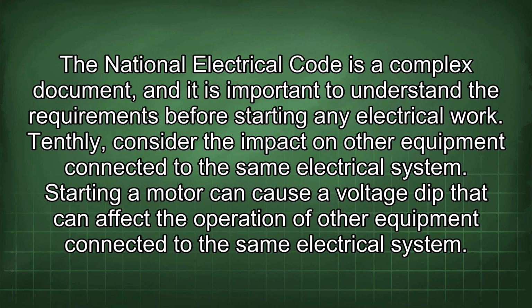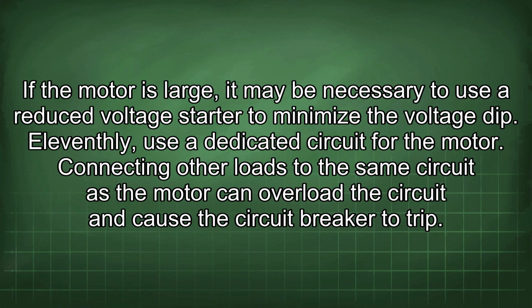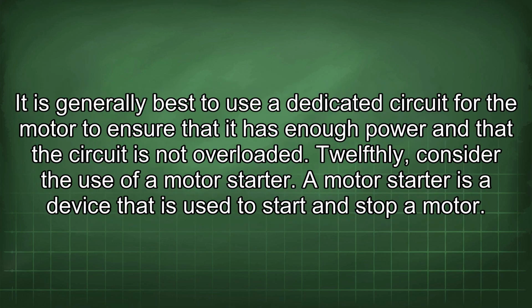Starting a motor can cause a voltage dip that can affect the operation of other equipment connected to the same electrical system. If the motor is large, it may be necessary to use a reduced voltage starter to minimize the voltage dip. 11thly, use a dedicated circuit for the motor. Connecting other loads to the same circuit as the motor can overload the circuit and cause the circuit breaker to trip. It is generally best to use a dedicated circuit for the motor to ensure that it has enough power and that the circuit is not overloaded.